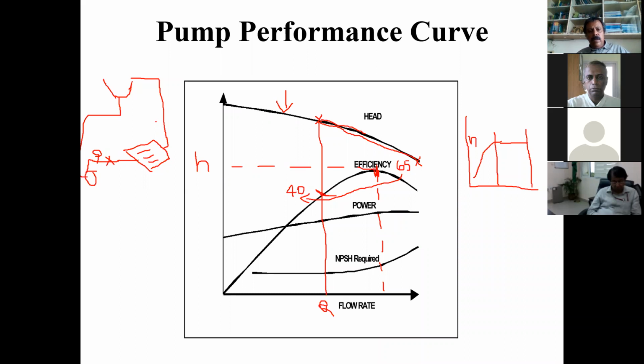So these are what are known as hidden losses. We don't know what is happening. The requirements are delivered by the pump, but at what efficiency, nobody knows. See, if it is lighting, for example, some lamps are on and nobody is there in the room, it's obvious. Visually, you can say that there is a loss. In this case, unless you measure various parameters and find out what is the operating efficiency of the pump, it will not be possible to determine how much energy we are losing by not operating at the best. This is called the best efficiency point, 65%.